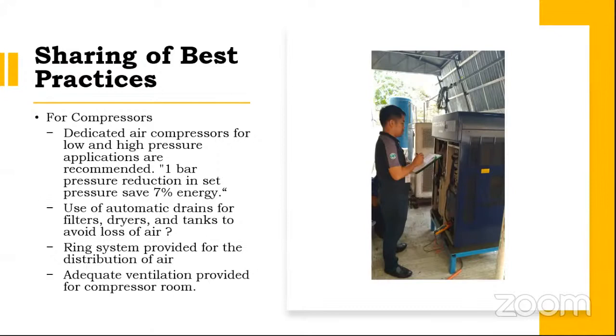We also use automatic drains for filters, dryers, and tanks to avoid loss of air. We also work on the piping system so air is distributed evenly. And we provide adequate ventilation for the compressor room, because the hotter the air the compressor takes in, the higher the energy it consumes.